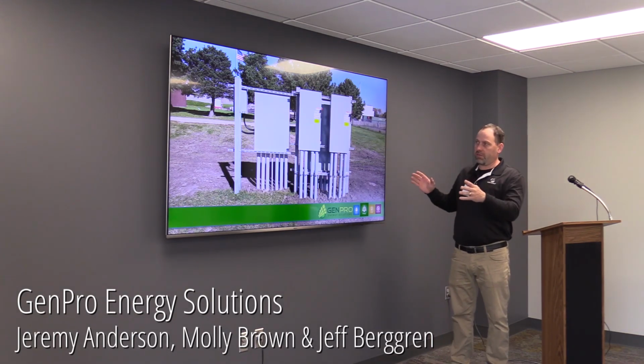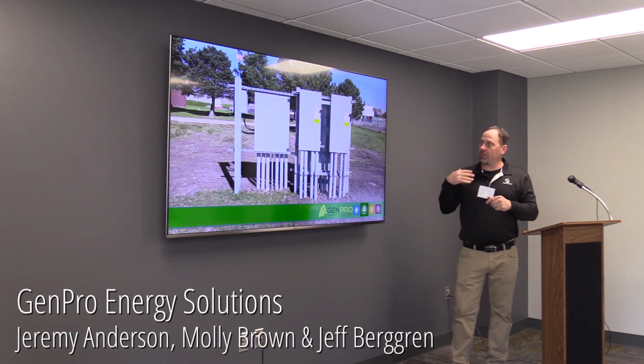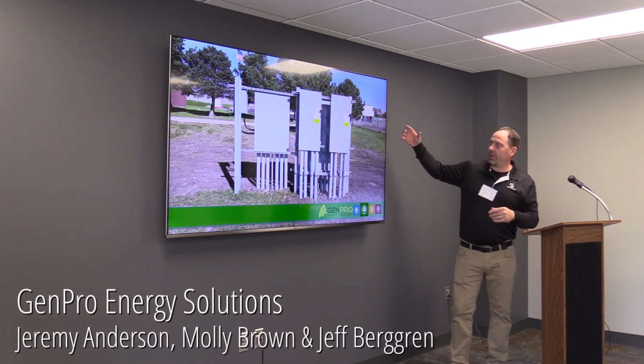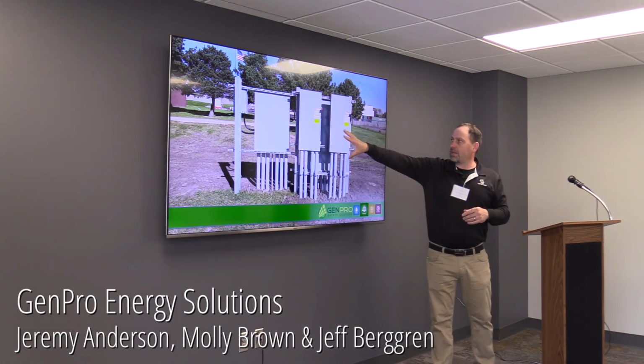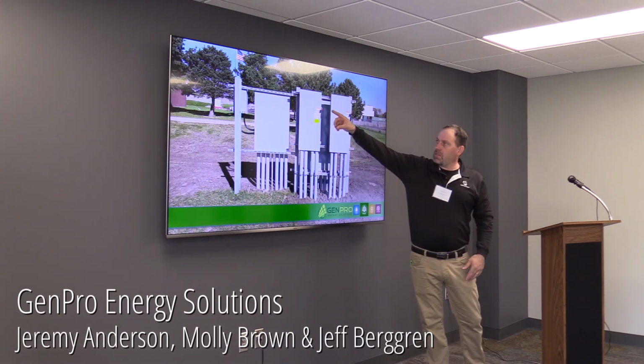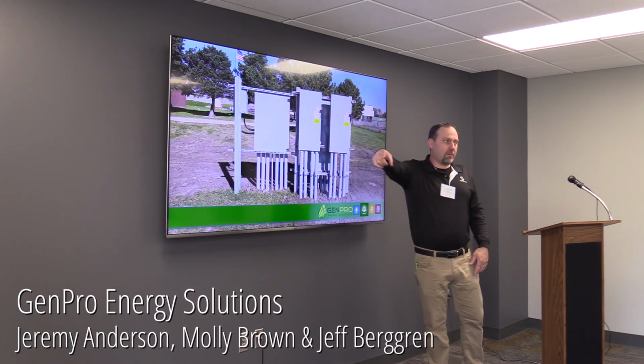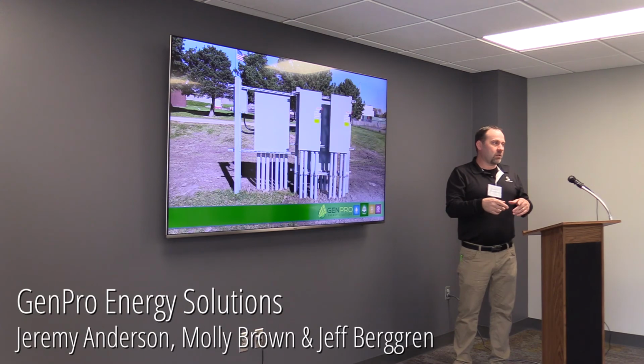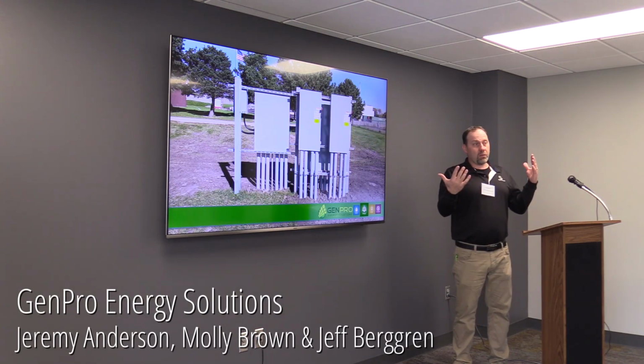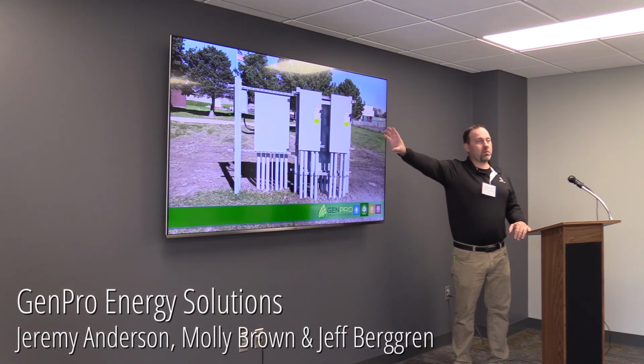This controls everything. So how the flow works is the flow comes through the solar panels, feeds through the inverters, back to these disconnects, through the SEL relay, back to the CT box, and back to the transformer. When it gets back to the transformer, they're metering that transformer 2 times. So they're metering the flow that's going out to the wastewater treatment facility, and how much flow they're pulling from the grid.